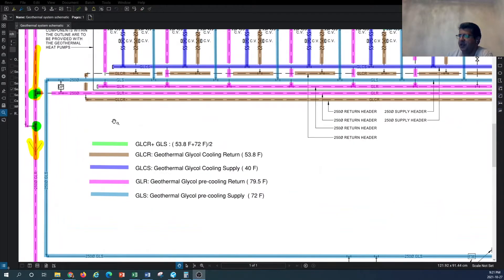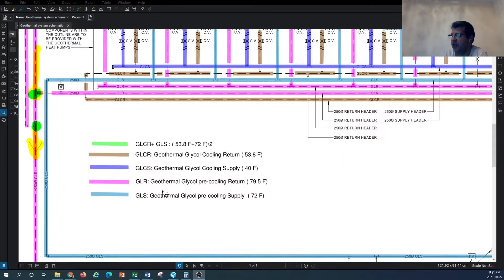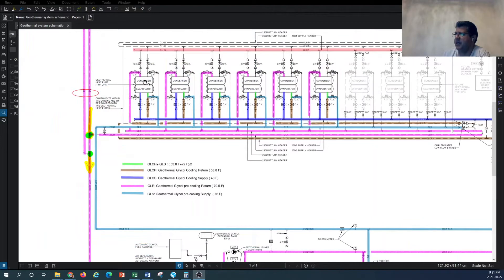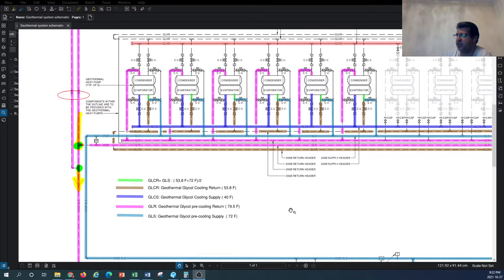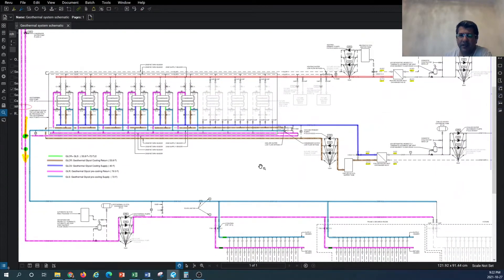Looking at the color coding, we have the geothermal glycol pre-cooling supply system and the geothermal glycol pre-cooling return, shown in pink. Then we have the geothermal cooling supply — this is the cooling glycol that comes out of the geothermal heat pumps, as you can see at the top, and it goes to feed the heat exchanger where we pick up the chilled water and distribute it in the building.